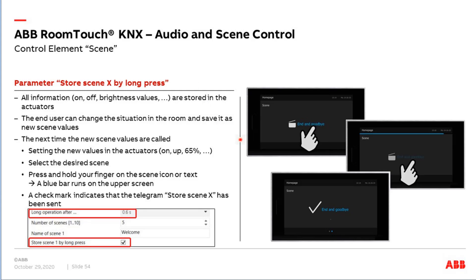Here's how to store a scene: the end user first sets the situation in the room — switches lights on, dims darker, drives the shutter to a position, and so on. Then they go to the scene, select it, press and hold their finger on the scene. A blue bar runs across the top and at the end a confirmation appears that the scene is saved. The RoomTouch sends the 'store scene' command. The difference is: short press calls the scene, long press stores it. To enable this you must set the parameter 'Store scene X by long press'. This allows the end user to change scenes between, for example, summer and winter with different lighting or shutter positions.